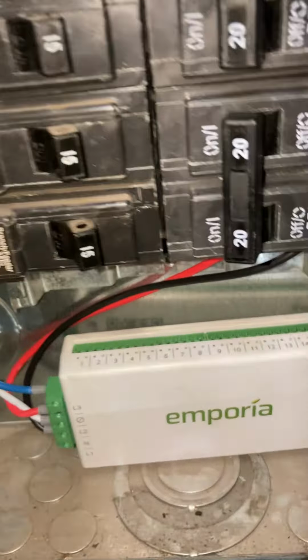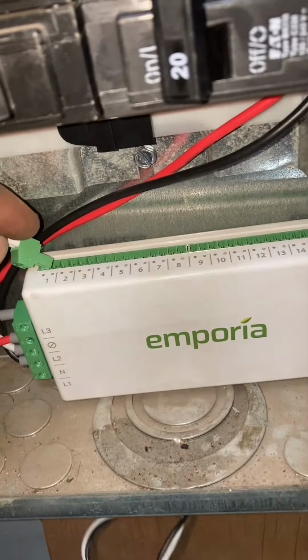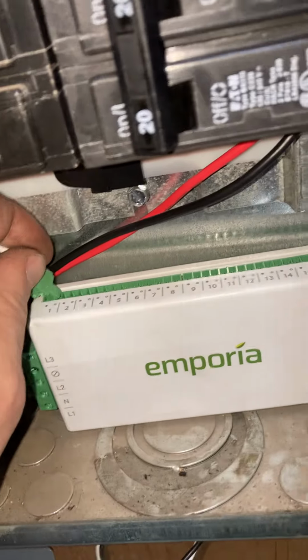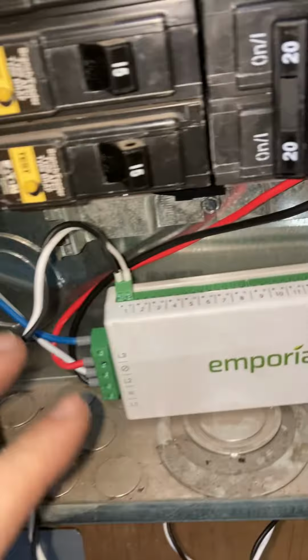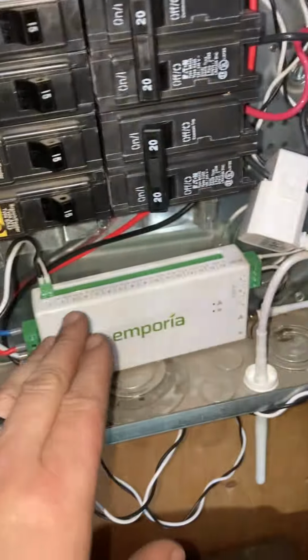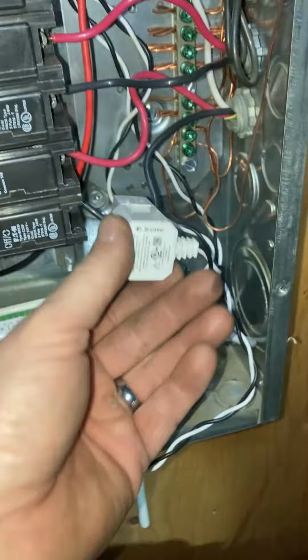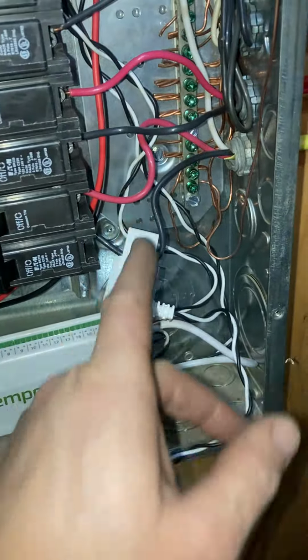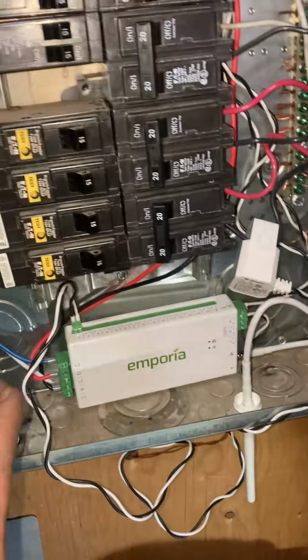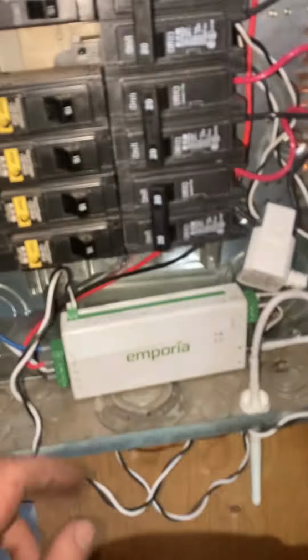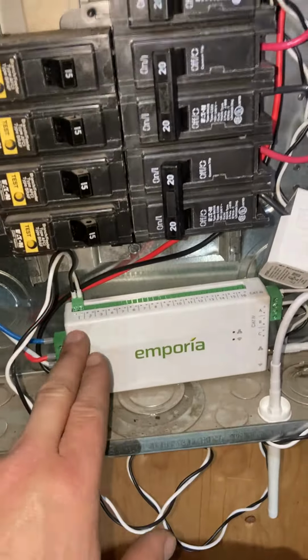And then we're going to plug this guy into one of the places on here, let's say number 1. Then in the app, when we're setting it up, you put in water heater, multiplier of 2, because it'll take that one and double it, assuming those loads are balanced, which on a water heater they typically are. Then it will have that one monitored separately, and it will do the math between what's coming in on the mains and this.